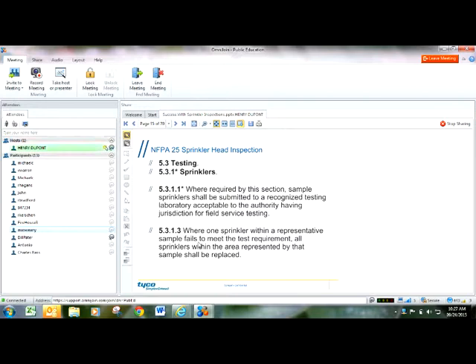UL will put the sprinkler head in what's called a hot box, and they put water pressure on it, the minimum required water pressure per that listing on that sprinkler head. They raise the heat up in that box, and if the sprinkler head goes off at the temperature that it was supposed to, it's considered a normal test. If the sprinkler head doesn't go off, or it goes off after the heat is well surpassed the required heat of the sprinkler head, it's considered an abnormal test.